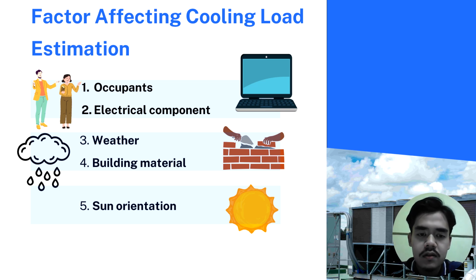After that is weather and building material. In a hot and humid country like Malaysia, the weather affects the heat gain a lot. For the building material, a design that has a lot of insulation, shading, and reflective material can lower heat gains significantly. A study showed that a well-insulated roof and envelope materials can halve the cooling loads when properly implemented.